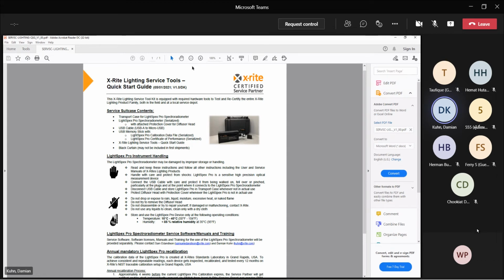You don't have to attach it for any sort of dark calibration. The method used on the Lightspex Pro is an internal shutter mechanism that will automatically block light from entering the sensor inside the instrument whenever a dark calibration is required. So there is no longer a manual dark calibration required. That's always triggered directly by the software, and it's done so fast that you hardly notice it. The only thing that helps you identify that it was done is a little clicking noise whenever the instrument opens or closes the shutter. Besides that, there is not really a delay in the whole process. It is done quite fast and almost not noticeable by the user.